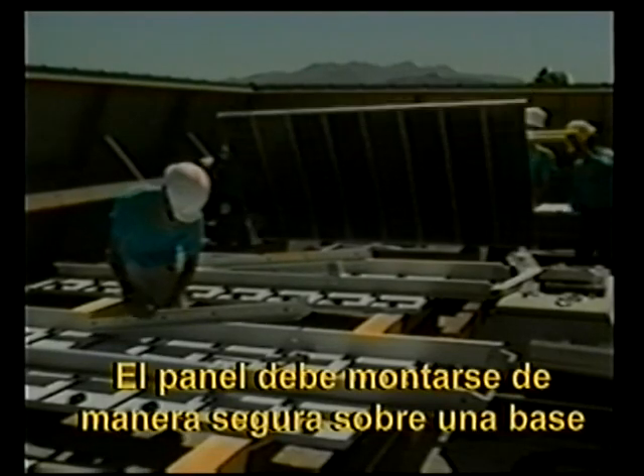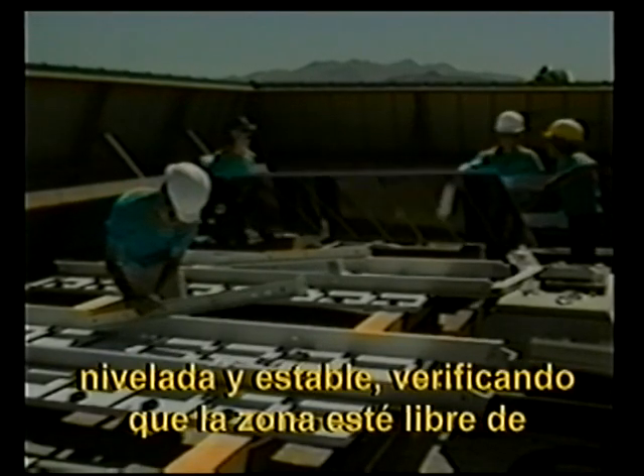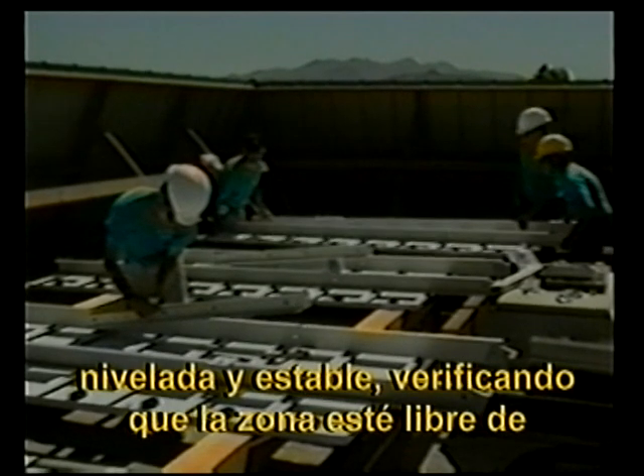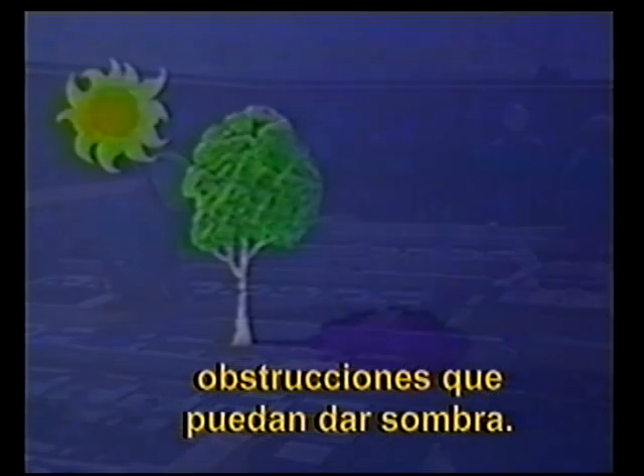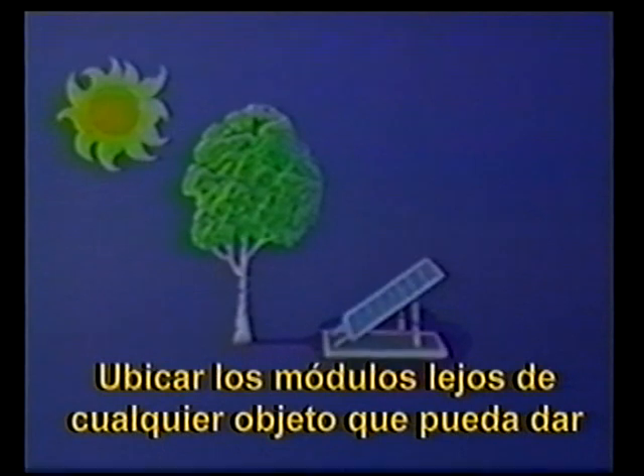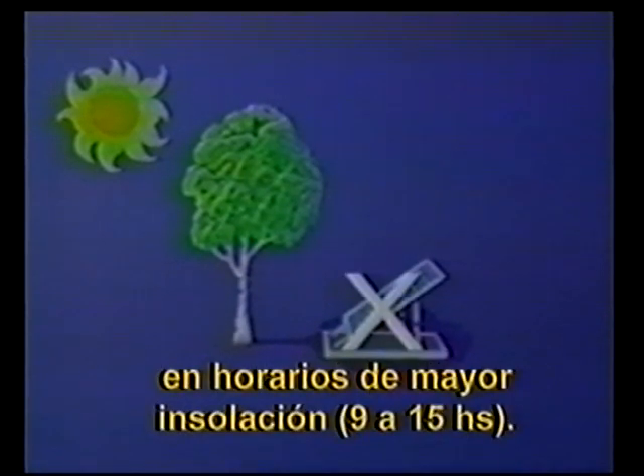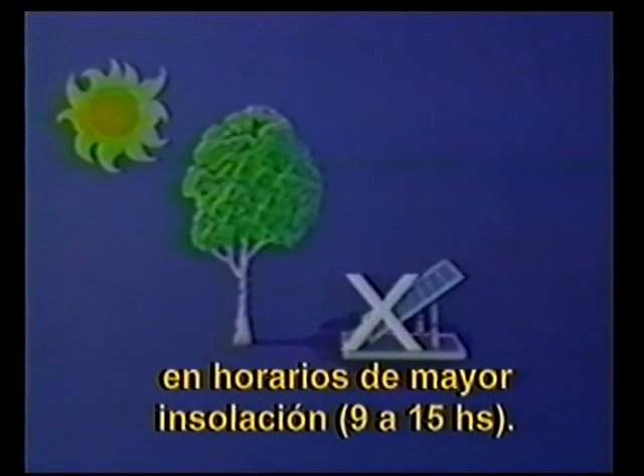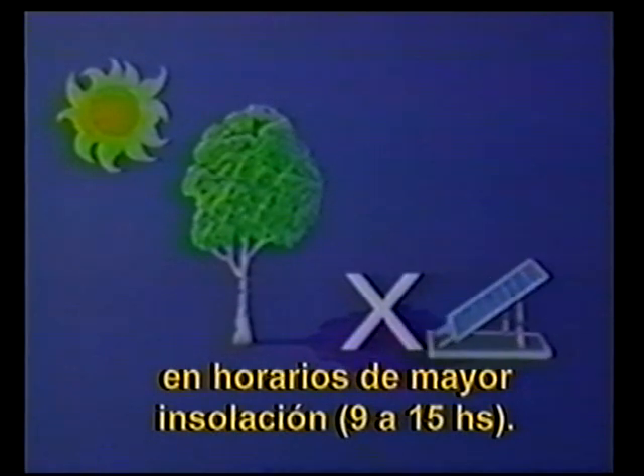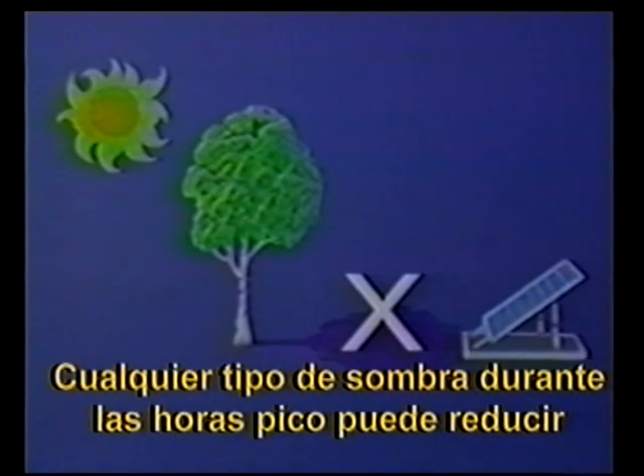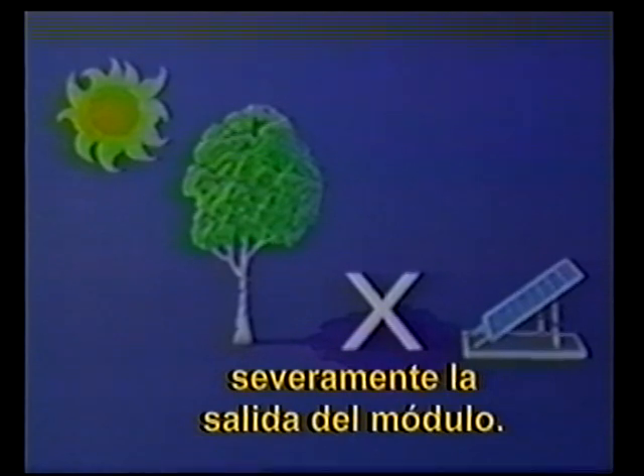The panel should be securely mounted on a level and stable foundation, making sure that the area is clear of obstructions that could cause shading. The modules should be positioned away from any objects that will cast shadows during peak daylight hours, from about 9 a.m. to 3 p.m. Any shading during peak hours can severely reduce module output.